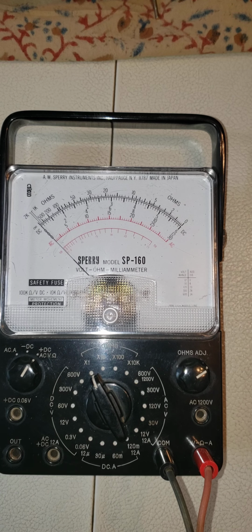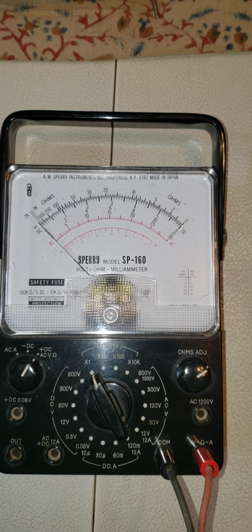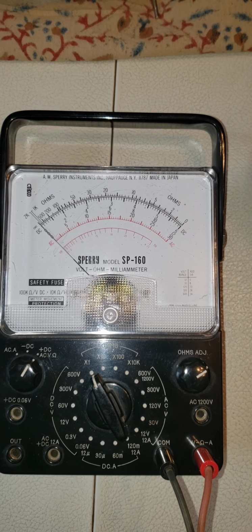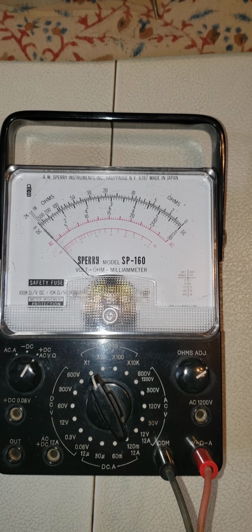And once you get used to reading your basic power cord, fuse, switch through the transformer and back to neutral with an analog meter, you will very quickly be able to tell whether the likelihood is that you have either a shorted transformer or a short, like in the power cord or the switch or something else downstream, even on the secondary side, that's causing your excess current draw.